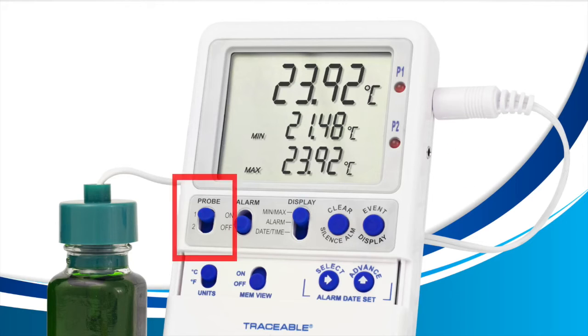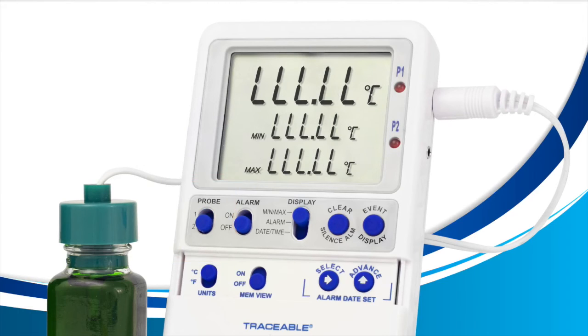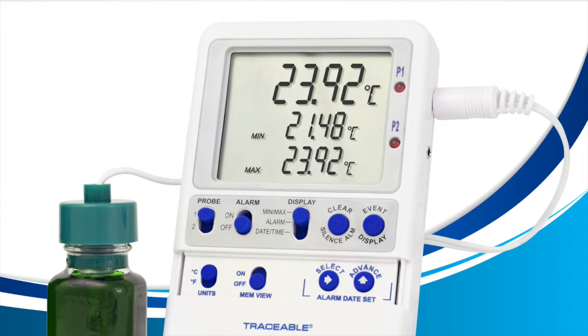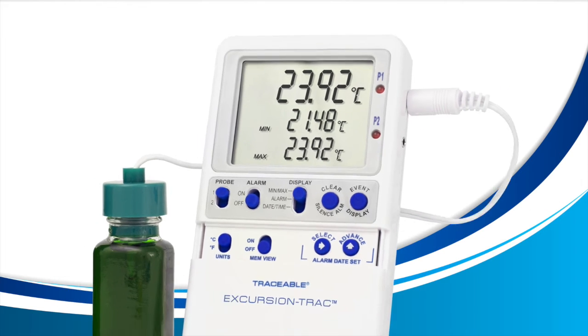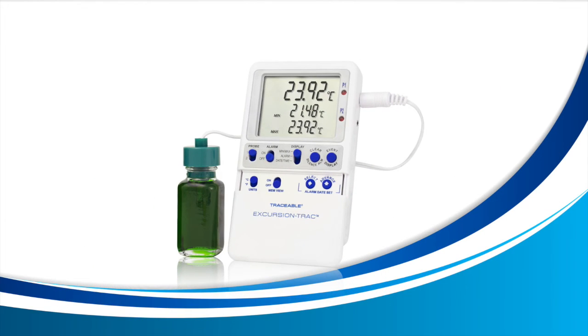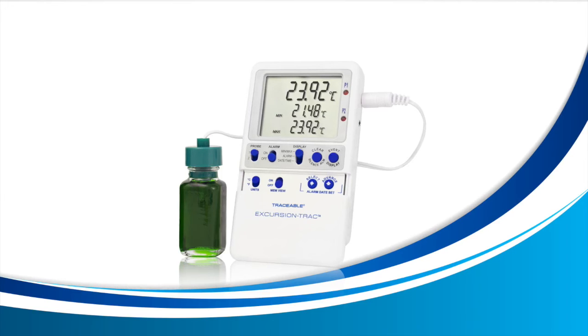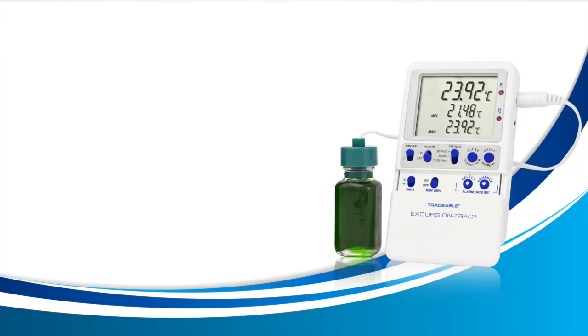If I move the probe switch to probe 2, my device will begin to read LLLLL as I don't have a second probe inserted into the probe 2 slot. If I move the probe switch back to probe 1, it will begin to work normally again as I do have a probe inside the probe 1 slot. Try this remedy and see if the LLLLL error goes away. If the error remains, let's try the third remedy.